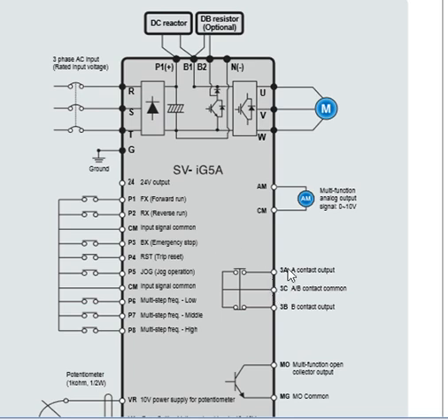Next, friends, on the right side down you can see 3 terminals. Written 3A, 3C and 3B. 3A is an output terminal, 3C is a common terminal, and 3B is an output terminal as well. Friends, this is a relay which has one normally open contact and one normally closed contact, 3A and 3B, and 3C is the common terminal. You can use this relay for many functions. You have to select in the parameters.